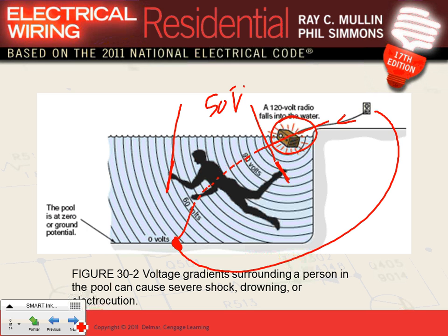At a high enough voltage, you get a voltage difference where this foot is sitting at, say, 5,000 volts and this foot is sitting at 2,000 volts. The difference between 5 and 2 is what? 3,000 volts. You will have 3,000 volts across your feet. Now, what happens if you have a voltage difference across two objects and you connect them together? You're going to have a current going right through you, and enough to kill you. There are a lot of stories.